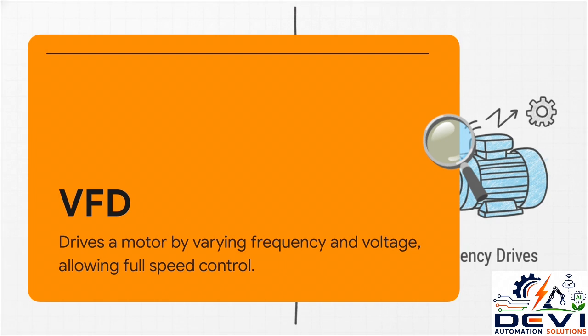Now contrast that with the VFD. This thing is fascinating. A variable frequency drive doesn't just manage the startup, it's a complete controller that drives an electric motor by varying both the frequency and the voltage of the power supply. This is a huge deal because it gives you full continuous speed control at literally any point during operation. Inside, it's packed with advanced parts, a rectifier to handle incoming power, a DC bus capacitor to smooth everything out, and an IGBT inverter to deliver that ultra-precise variable frequency directly to the motor.